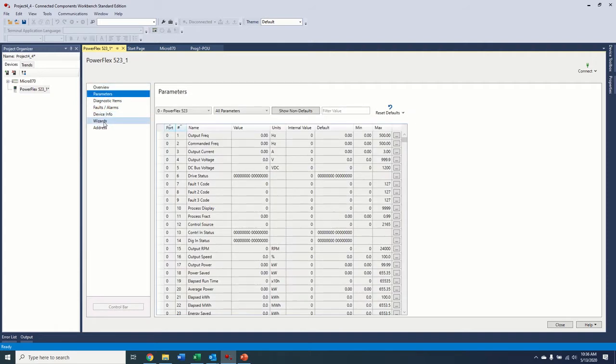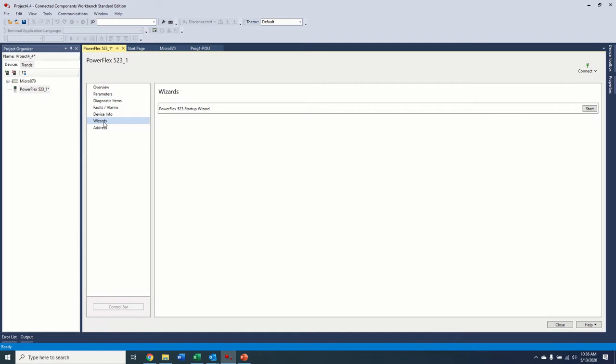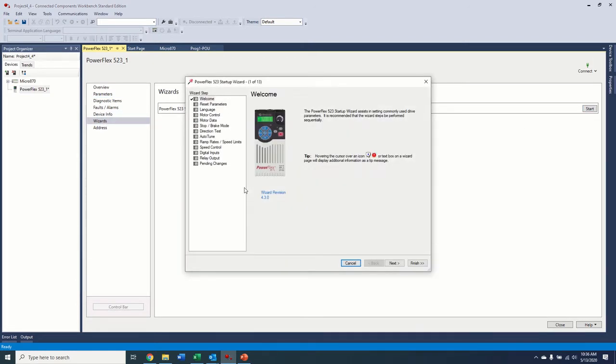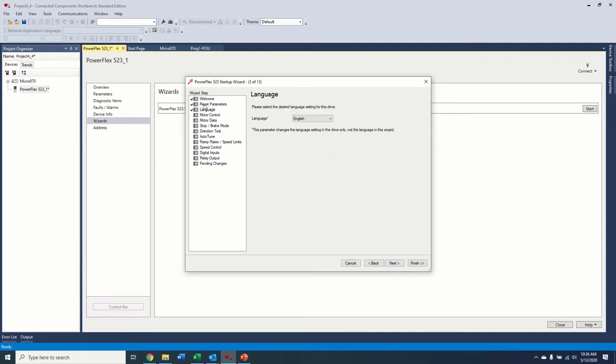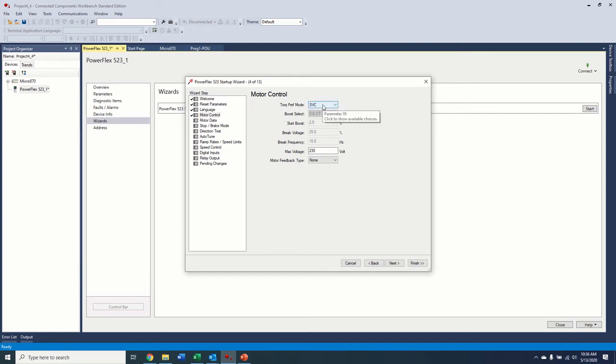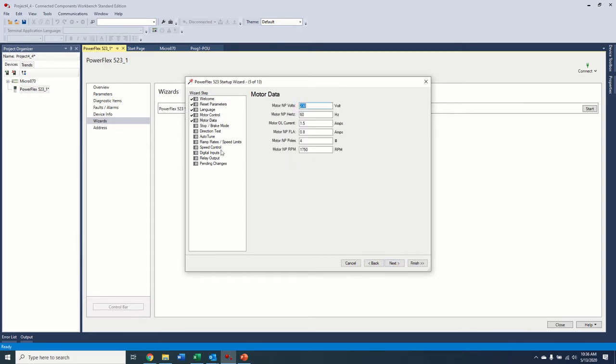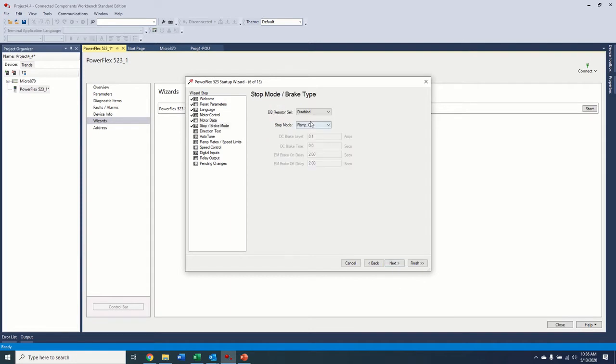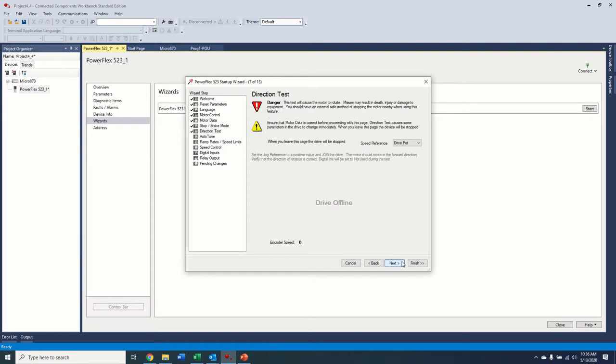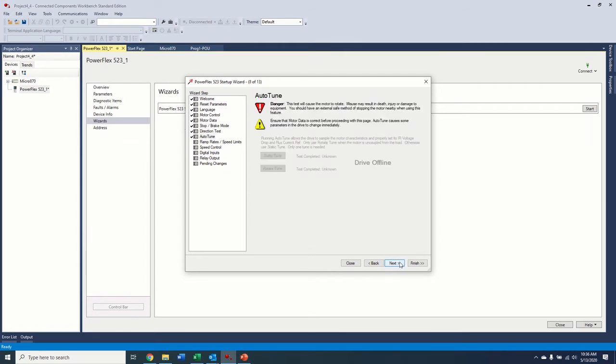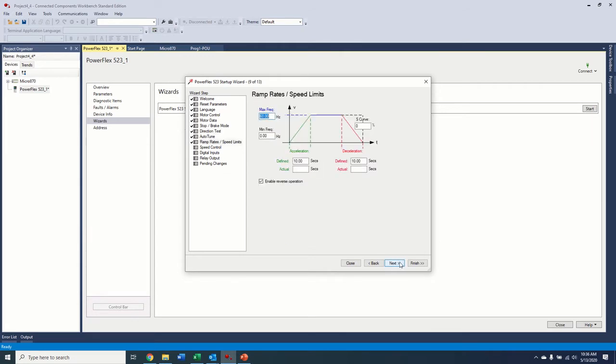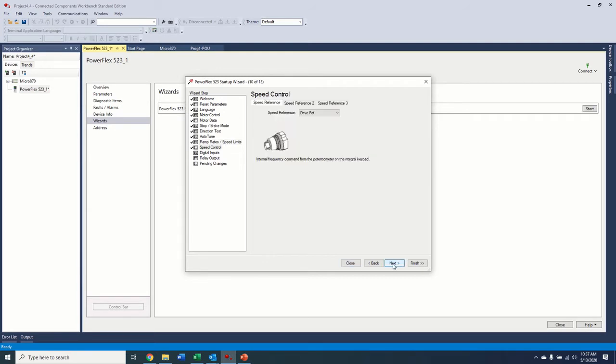The other thing I wanted to point out was wizards here. This startup wizard is a very nice tool when pulling a drive out of the box. Instead of going through the startup on the HIM module, this startup wizard can step you through the main steps without you having to hunt down any parameters. As long as you just keep hitting next, you can select simple motor control, vector, volts per Hertz, your voltage information, and then your motor nameplate data.